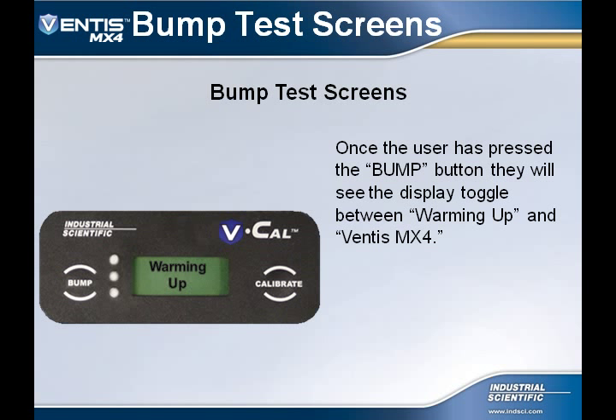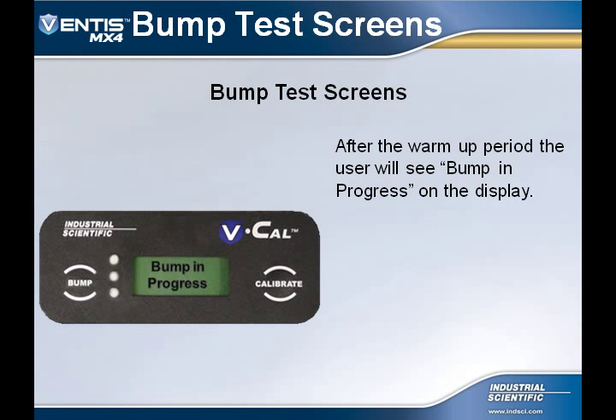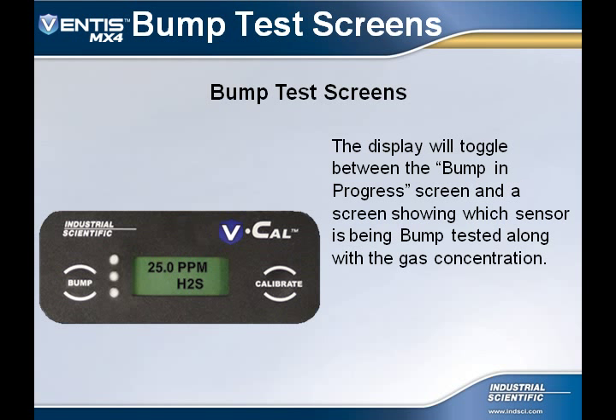The VCal's display will toggle between warming up and Ventis MX4. After the warm-up period, the VCal's display will show bump in progress. The display will toggle between bump in progress and the sensor type being tested, along with its bump gas concentration. The display will then toggle between bump in progress and the next sensor being tested, as well as its bump gas concentration.